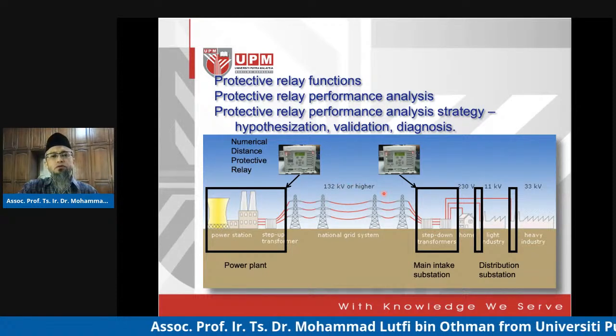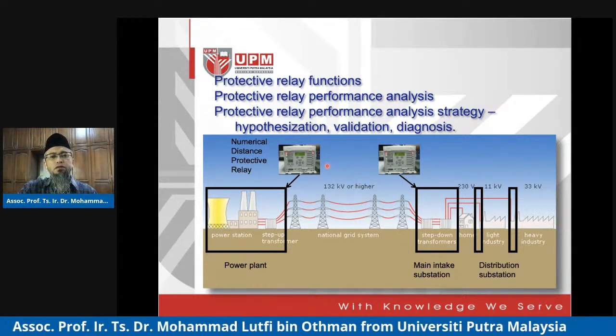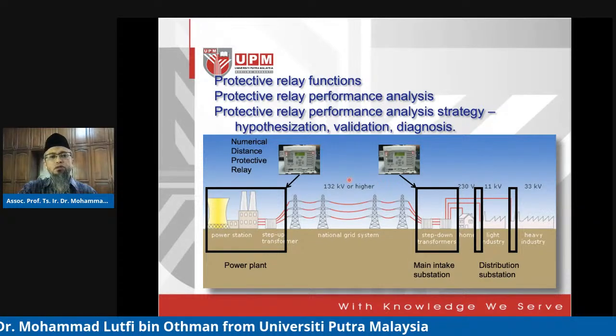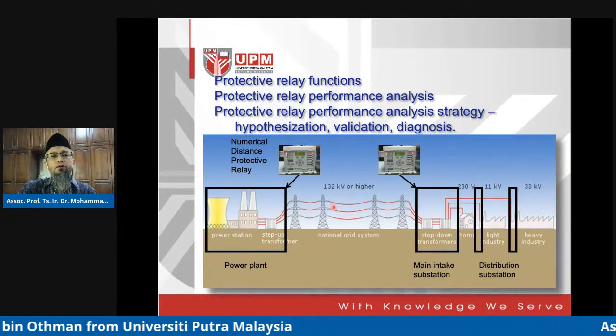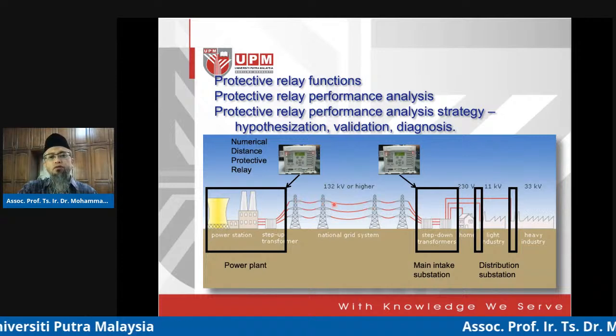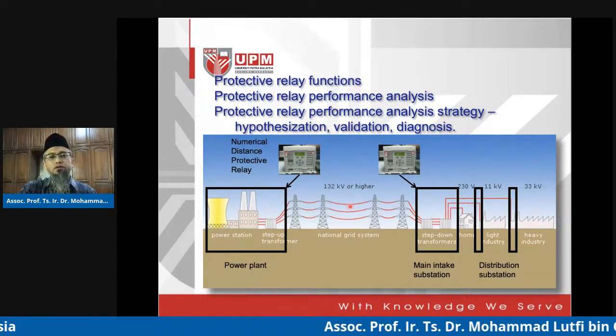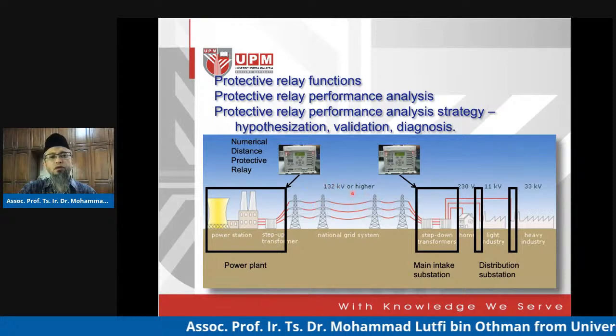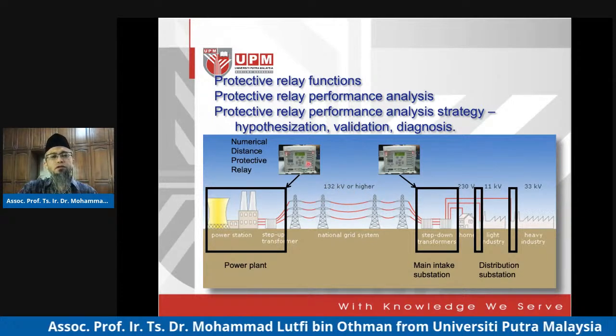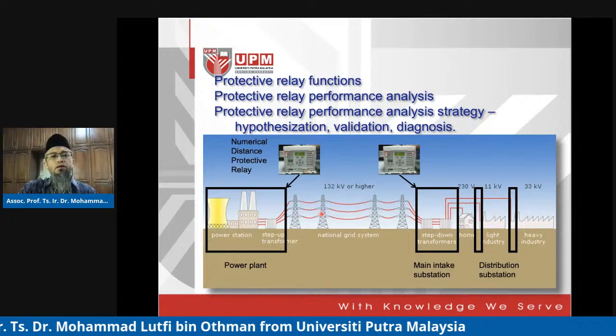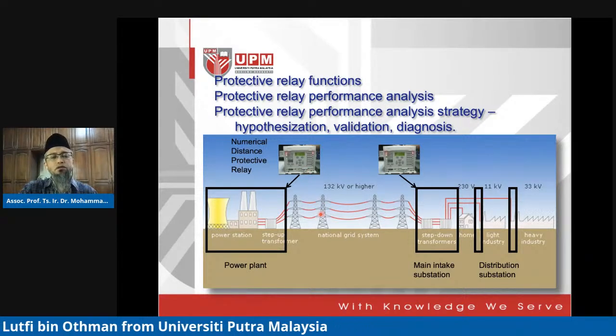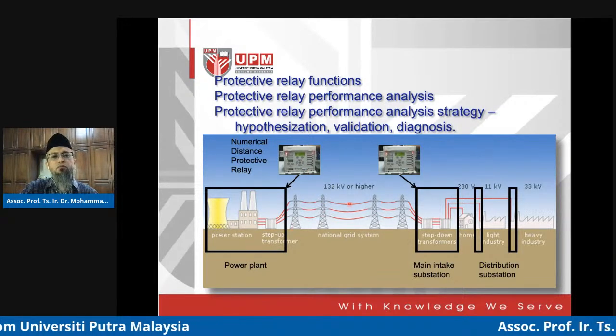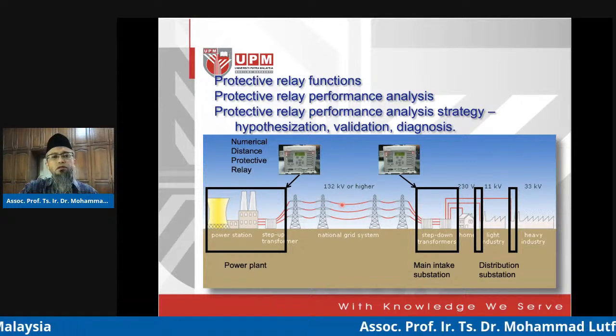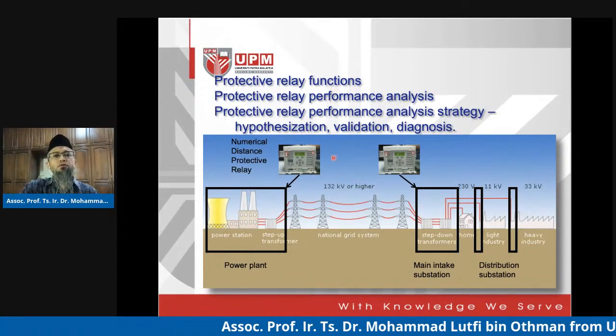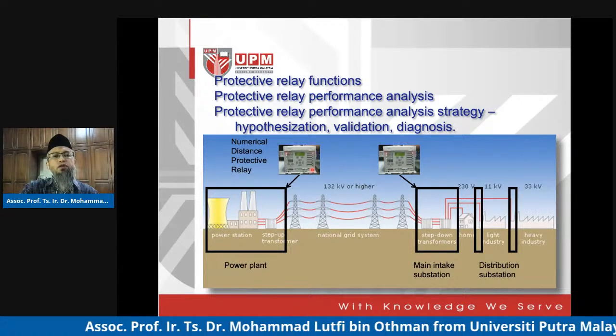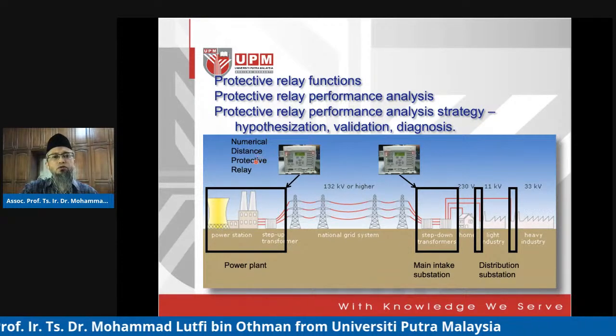So what they do is interact in a coordinated manner to operate and protect the transmission line for whatever kind of fault, wherever it is located near or far from any one of them. The device detects and operates by giving out the tripping signal to circuit breakers to finally open whichever transmission line is found to be faulty. That's basically the function of one of many protective devices—distance protective relays.